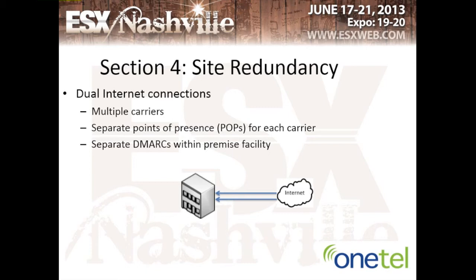So when you drop separate internet connections in your facility, it's very important to ask, where is that point of presence outside my building? How far is it away? How is it leaving my building? A lot of people throw separate demarcs into their building in different locations, so if they have a fire in one part of the building, all their demarcs aren't completely ruined. They have additional power over here, different battery backups, to have that kind of redundancy within their own facility.